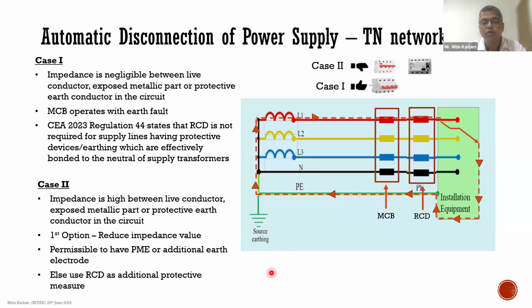It is also permissible to have an additional PME or additional earth electrode. And if still the MCB is not tripping, the fault loop impedance value is not sufficiently low, then it is a must to have an RCD connected in the circuit so that the equipment does not stay live in case of fault, or does not get heated up and there are chances of fire.